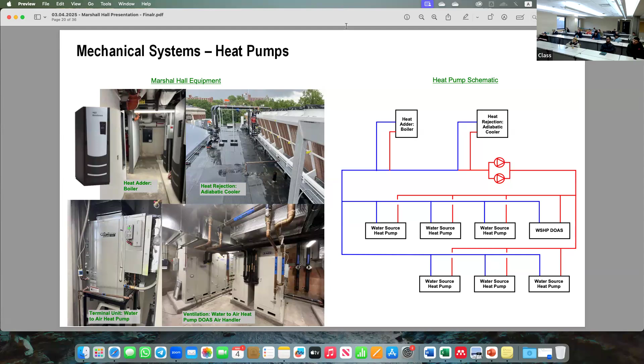We paired up this system with the boilers, which we talked about a little bit, and then for cooling, you need somewhere to reject any excess heat. So what we have on this building is an adiabatic cooler. Basically, you pump your water up there, and anytime it's too hot, that adiabatic cooler has air fans that move an incredible amount of air through a coil. And there's actually a wetted pad on the front of that that helps to cool that air even more, so that you get some of that latent capacity instead of just sensible. So those are what are rejecting any excess heat from the building out to the atmosphere, so that we're keeping that heat pump loop in range. For context, the heat pump loop can vary between the 40s all the way up to the 80s. So you really have a pretty wide range of flex in there where the heat pumps can be sharing load without turning those pieces of equipment on.